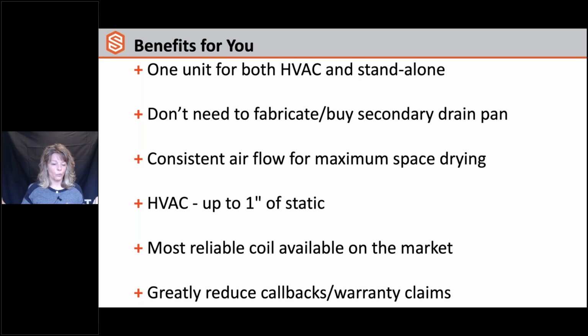Again, static up to 1 inch for HVAC. That's a game changer, especially with a lot of these high static, energy efficient HVAC systems on the market, as well as what we're seeing more and more, homes with ducted or ductless mini splits. So being able to provide that maximum airflow by giving the dehumidifier its own ductwork, which typically is at least 3 supply trunks, that'll help a lot.